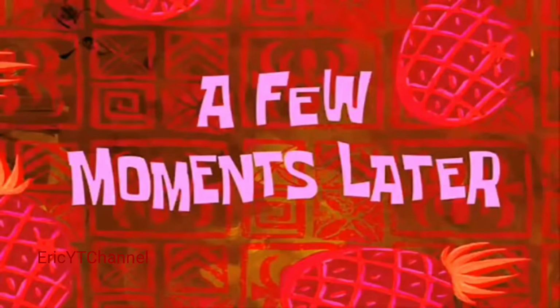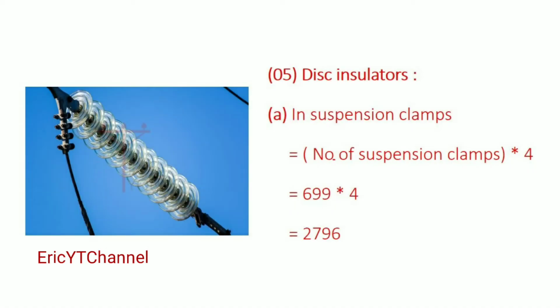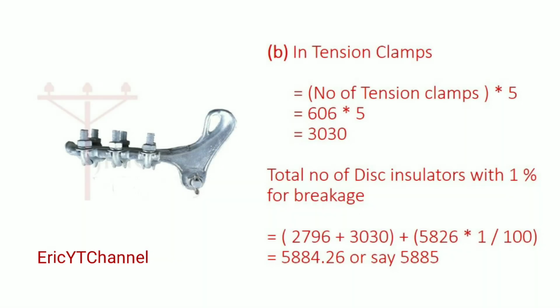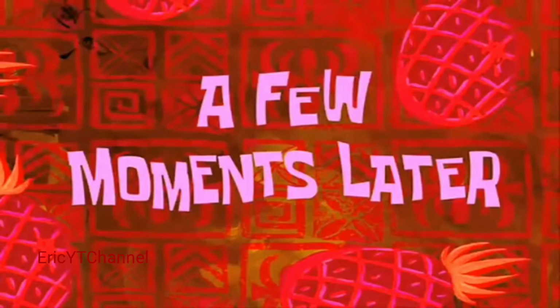Number 5 is disc insulators. Letter A, in suspension clamps equals number of suspension clamps times 4 equals 699 times 4 equals 2796. B, in tension clamps equals number of tension clamps times 5 equals 606 times 5 equals 3030. Total number of disc insulators with 1% for breakage equals 2796 plus 3030 plus (5826 times 1 over 100) equals 5884.26, or say 5885.